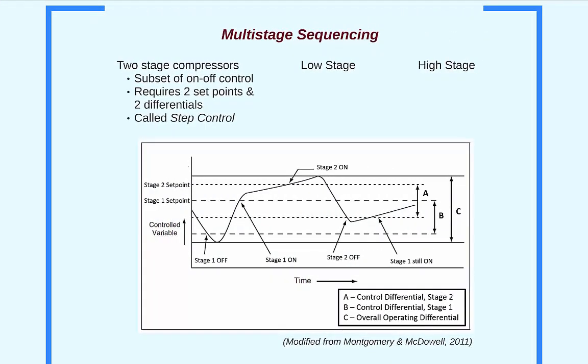Perhaps you've heard of two-stage compressors or have one installed at your home. Two-stage compressors have a low stage and a high stage, providing two different capacities. The low stage might be sized to handle 60% of the design capacity, and when the high stage turns on, the compressor provides the total capacity. The high stage only kicks on when the low stage can't maintain set point. Two-stage control is really a subset of on-off control, which requires two set points and two differentials. In HVAC systems, it's employed often enough that we give it a unique name. We refer to it as step control.